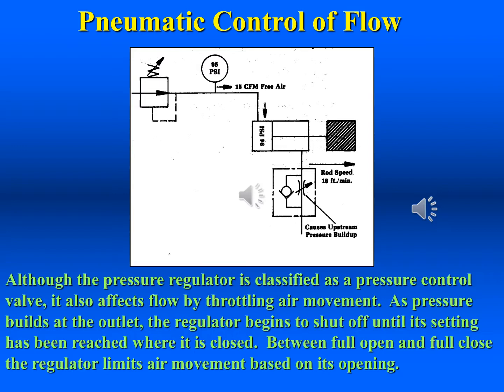Flow controls do the same job in pneumatic systems as they do in hydraulic systems. However, a pressure regulator is a pneumatic pressure control usually found in branch circuits leading up to equipment, and they also affect flow rate. The regulator is normally passing, and as it closes, causes a slowing of the airflow and a drop in pressure known as pressure droop. Therefore, it is necessary to consider the adjustment of both the flow control and the regulator to achieve optimum speed control in compressed air systems.